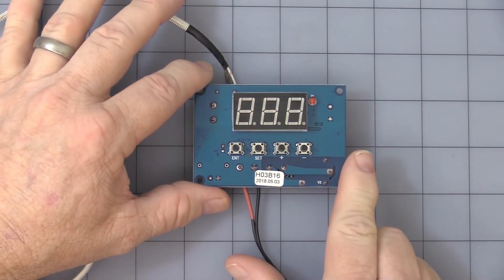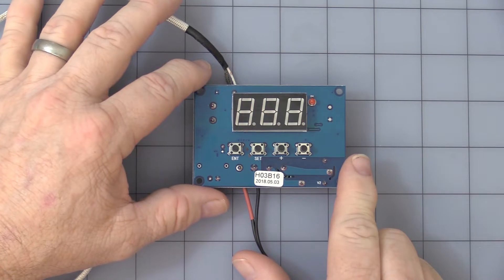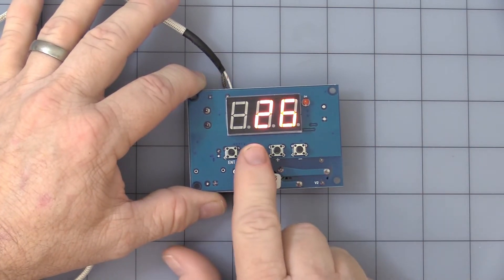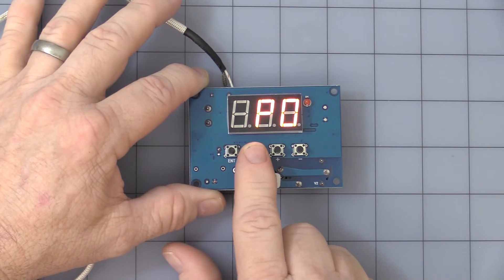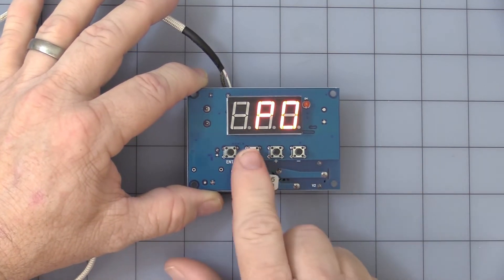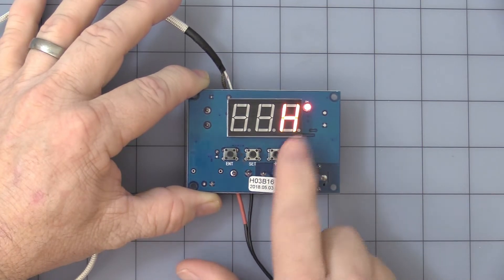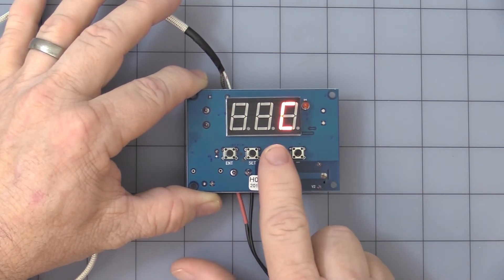Now that's the set point. Now it can be used for heating or cooling. I'll show you how to get into programming of that. On the set button, you press and hold, and it says P0. Hit set again, and you see it's C for cooling, H for heat, back and forth.